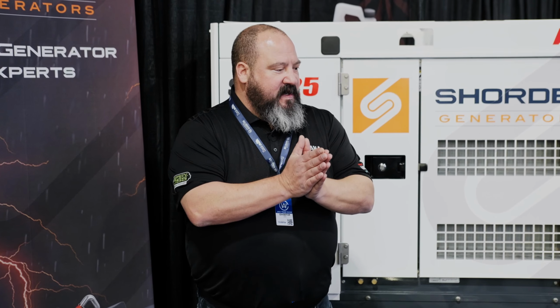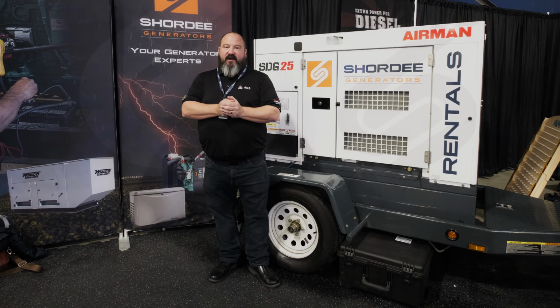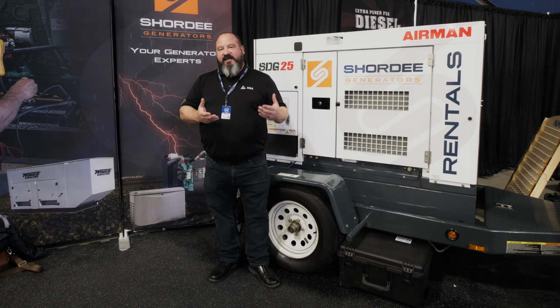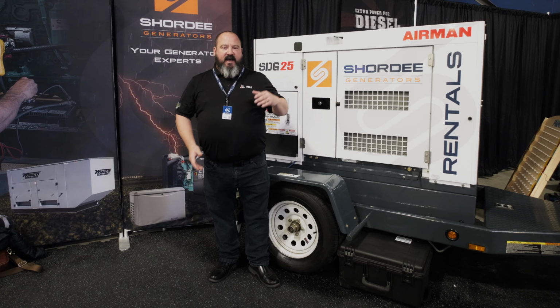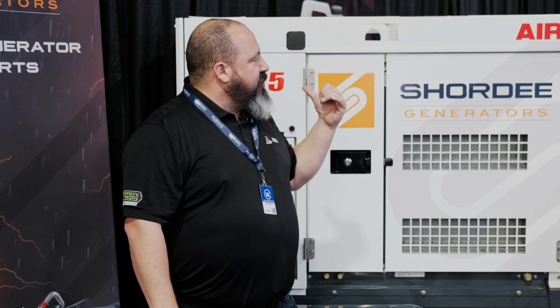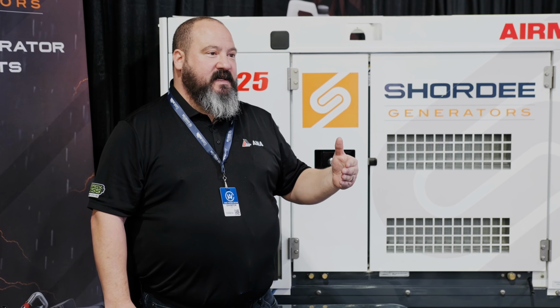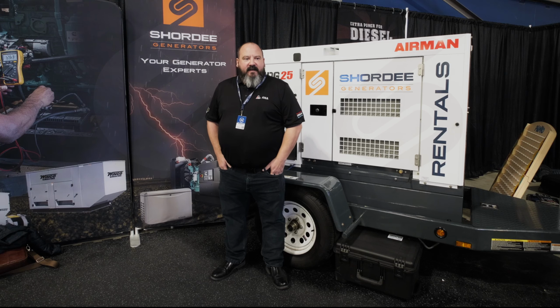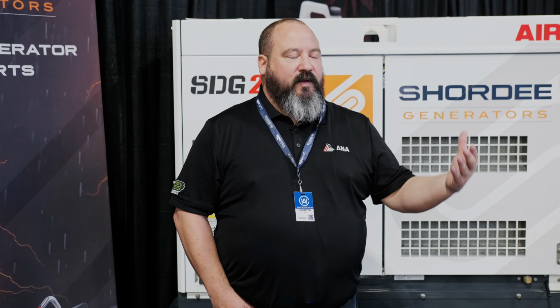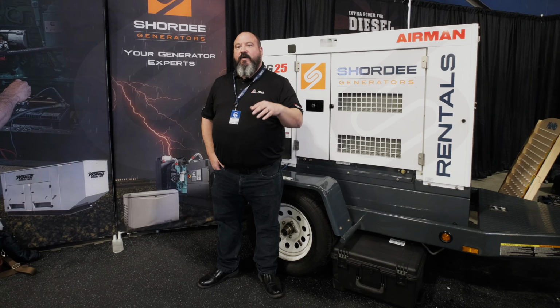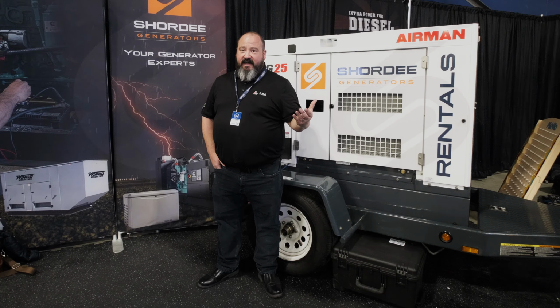We also have the pride of our company, and that is our eBOS offering, which is a hybrid generator system. What that is, is a battery system out front, our eBOS battery, in conjunction with our generators to give you a true seamless hybrid diesel generator system. The advantage of our hybrid system is when you are working in a situation where you have high peak load but low average load, what you end up with on today's Tier 4 gensets, and with a lot of gensets overall, is what's called light loading. It's where the generator doesn't see enough load to stay hot and it causes issues with the emission systems. They'll start to wet stack, so oil and fuel will come out, damaging the emission system.